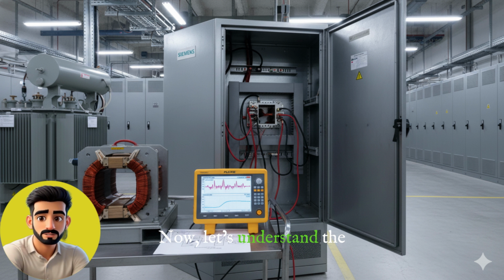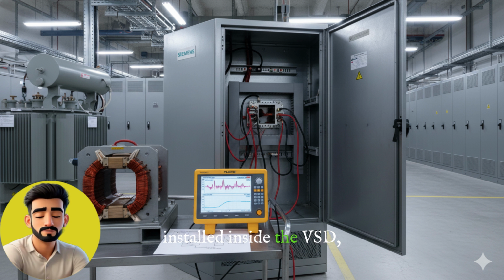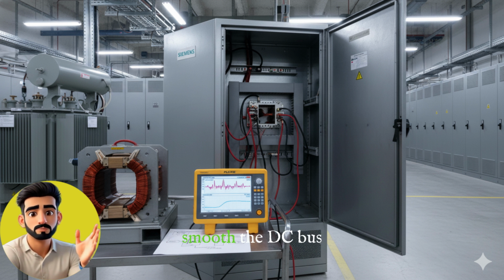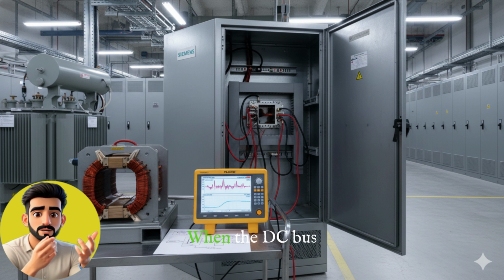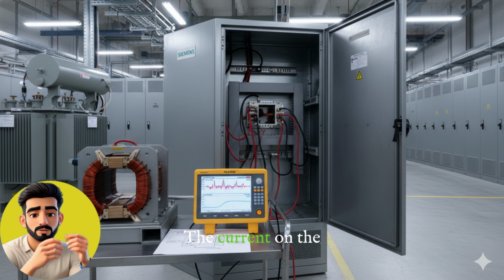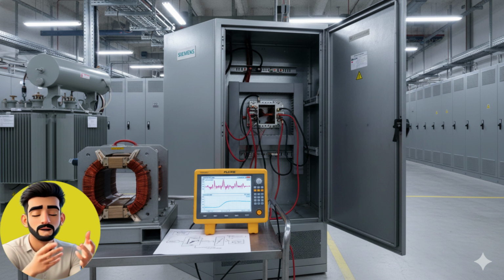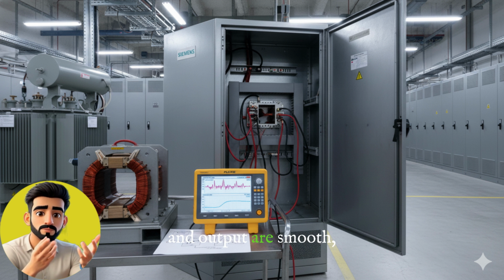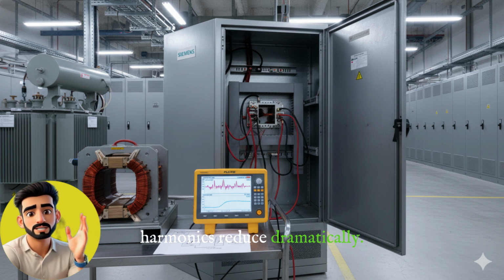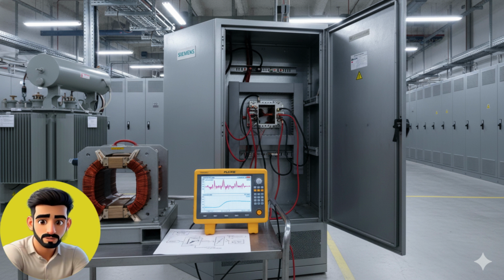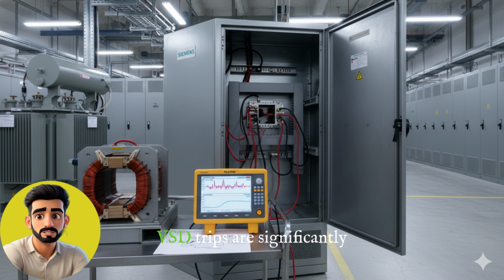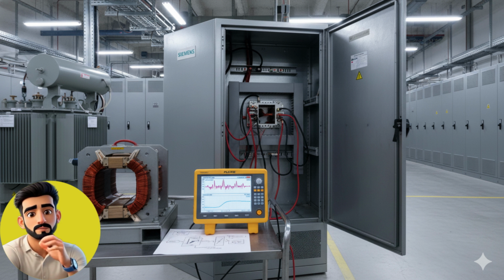Now, let's understand the DC choke. The DC choke is installed inside the VSD, whose function is to smooth the DC bus current. When the DC bus is smooth, the current on the inverter side is also smooth, and when both input and output are smooth, harmonics reduce dramatically. With the DC choke, the drive's lifespan increases, motor heating decreases, and VSD trips are significantly reduced.